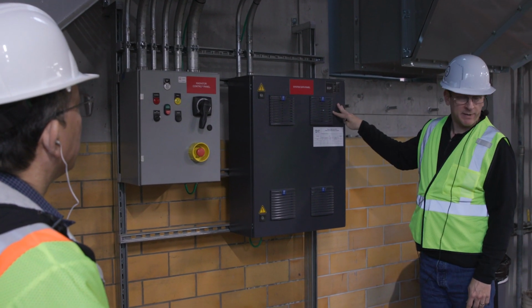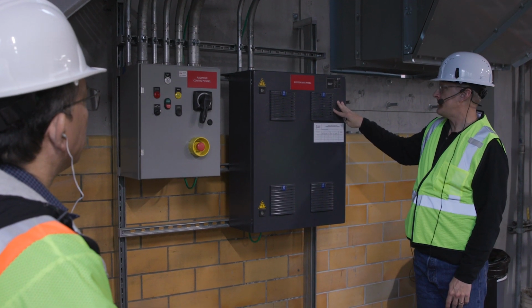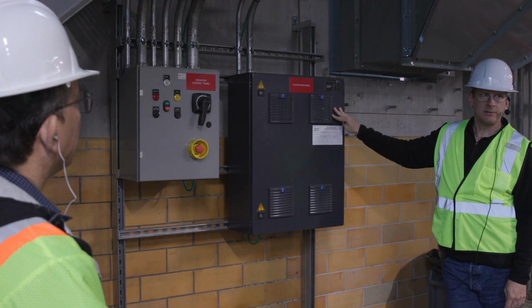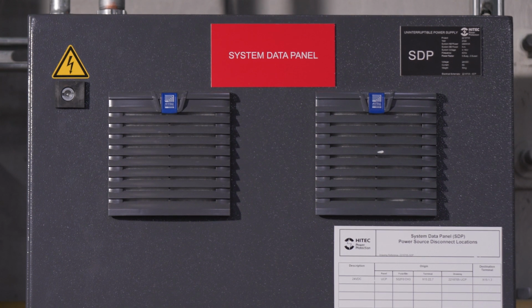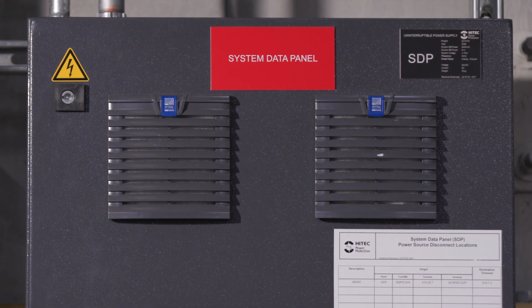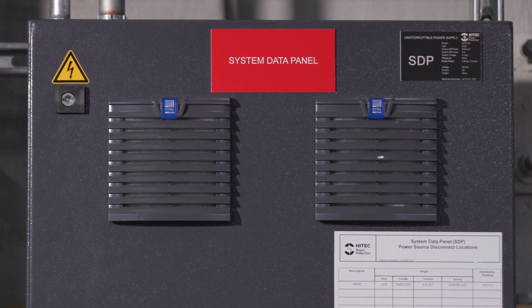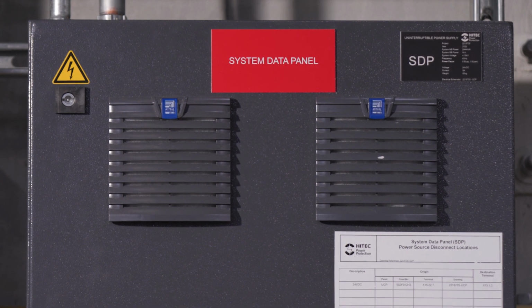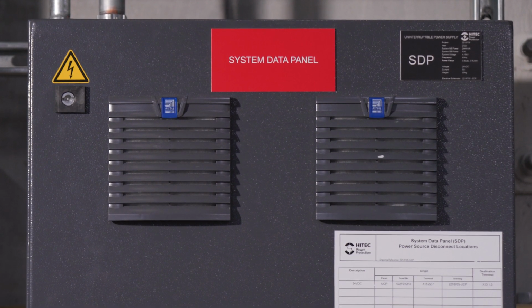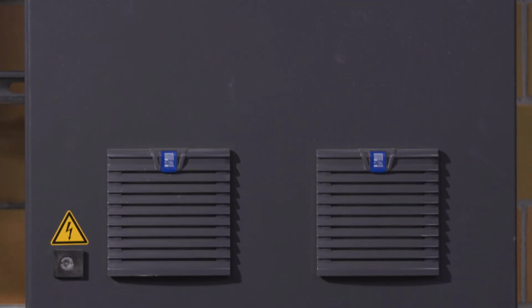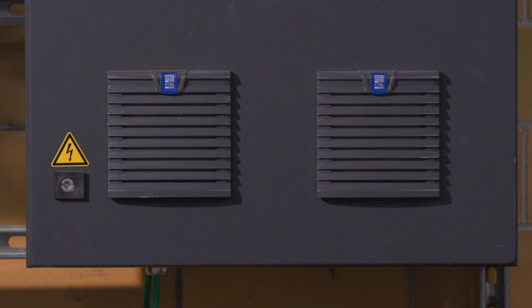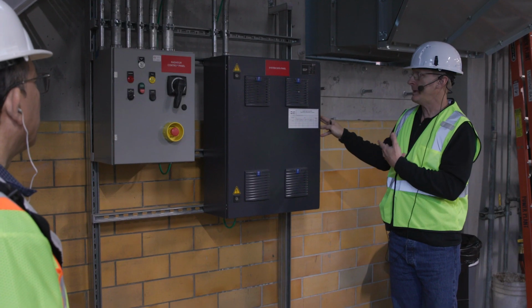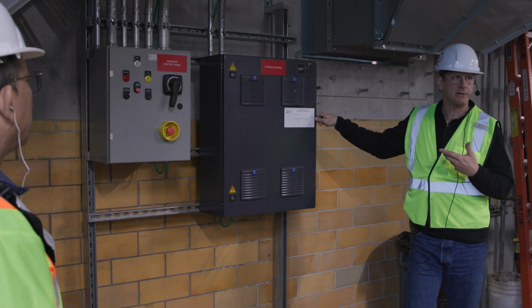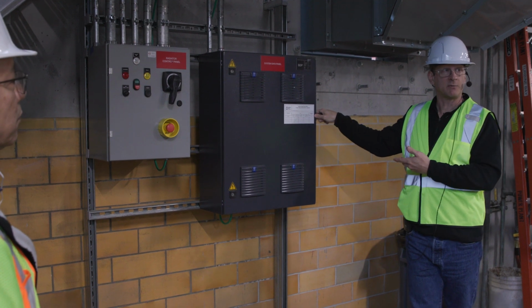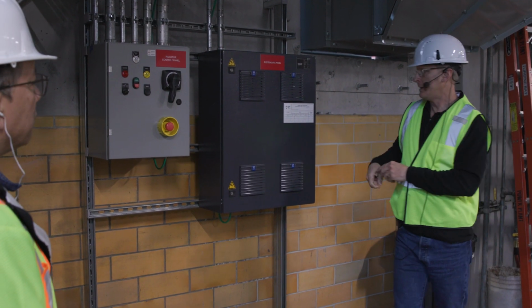All right, system data panel. This is a separate SCADA monitoring panel. It's separate from the other controls, and basically it has nothing to do with the operation of the system other than its monitoring. But it allows the customer to come in and extract information to their BMS through this panel. But also, you can use the SCADA function if you want. Running our SCADA client on a laptop, you can actually monitor the system through SCADA as well, and some control as well.